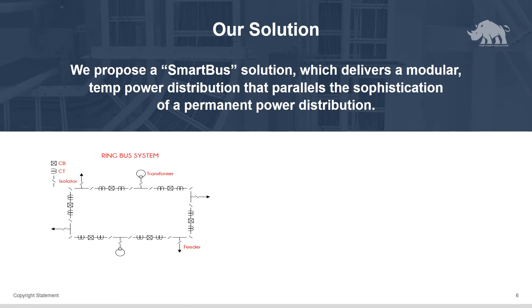We propose a smart bus solution which delivers a modular temp power distribution that parallels the sophistication of a permanent power distribution. With a smart bus, we can proactively monitor the health of our system with integral CTs, current transformers, and PTs, potential transformers. All of this analog data will be fed back via fiber optic cables to PLCs, programmable logic controllers, to capture data for historian and alarm monitoring.